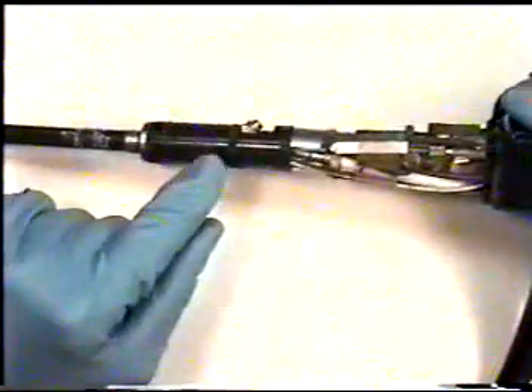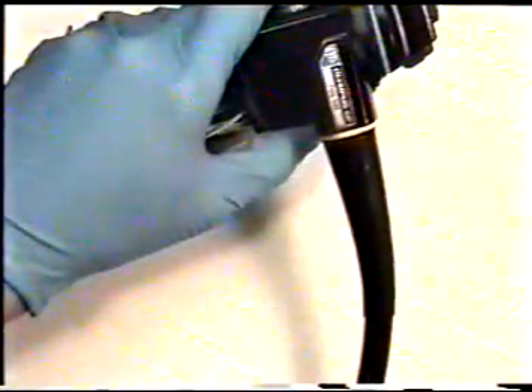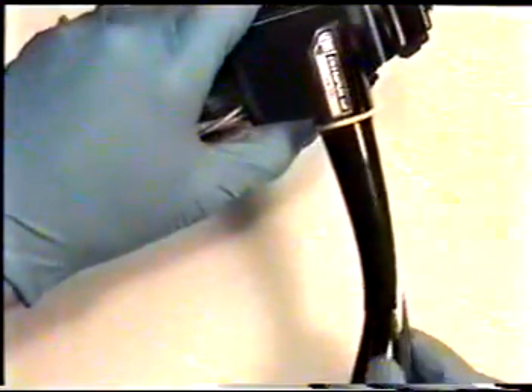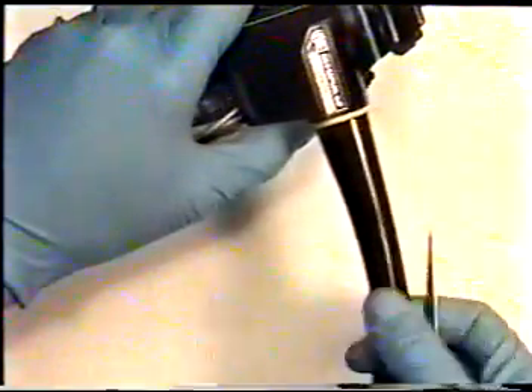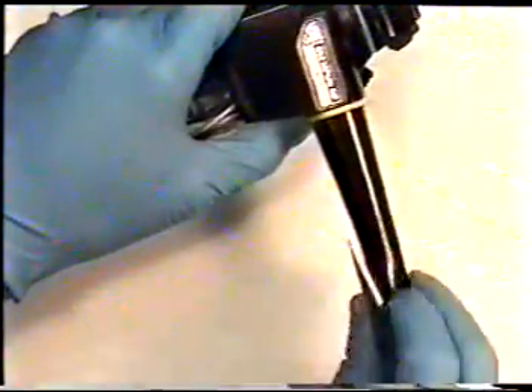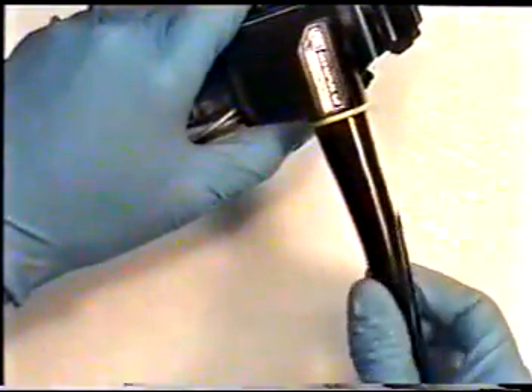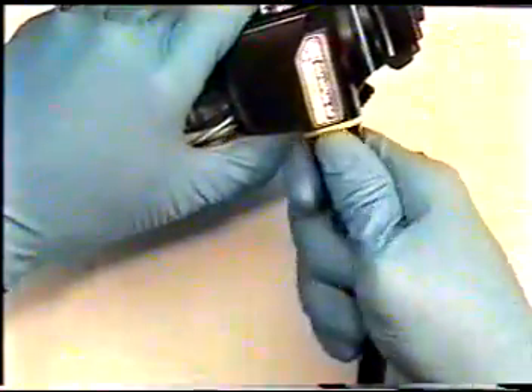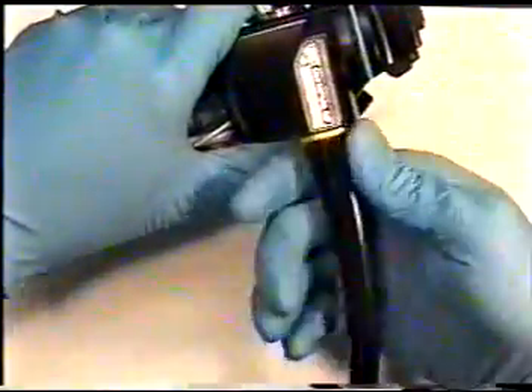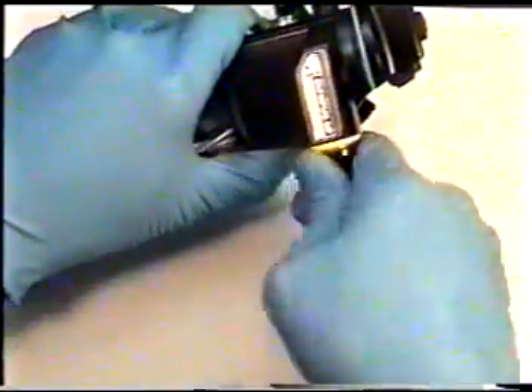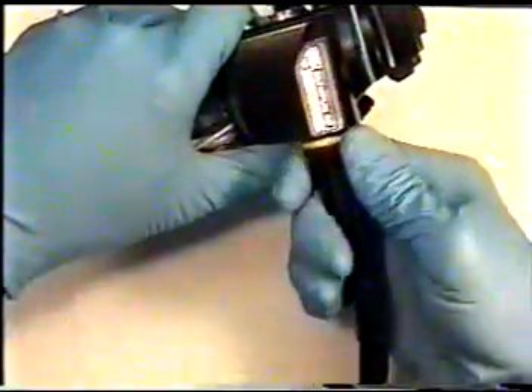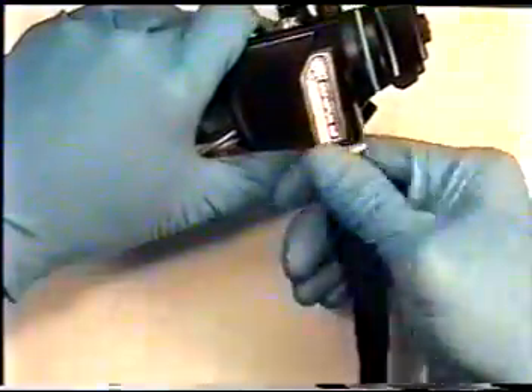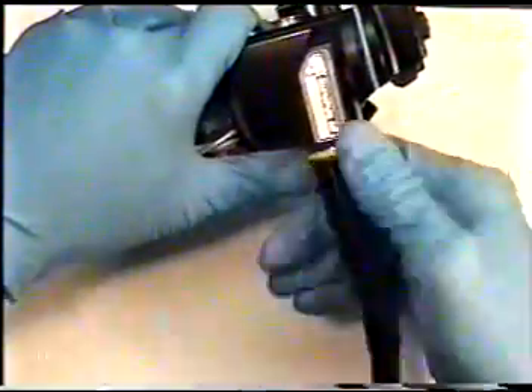We now have access to the internal body of this Olympus endoscope. Using a dull pair of tweezers and some alcohol, slide alcohol underneath the cone of the light guide tube. Unscrew the light guide tube cone or boot. And slide down the light guide tube approximately 12 inches.